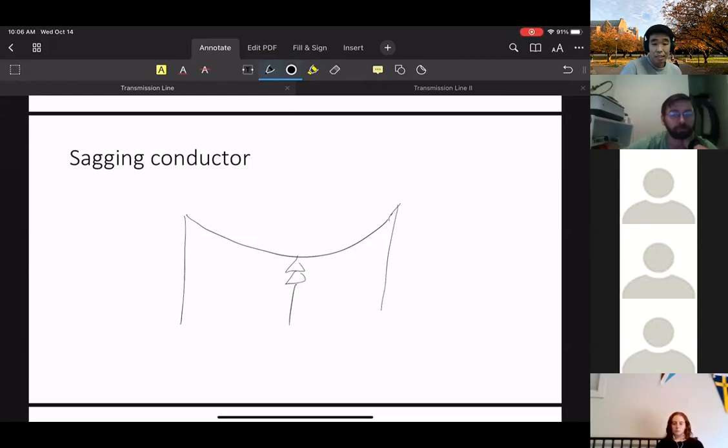That's why we have current limits on transmission lines. The current limit on transmission lines is not when you will melt the transmission line. It's very hard to melt a transmission line; you need a lot of current to do that. What happens, at least for these overhead transmission lines, is that the current limit exists because you don't want the lines to sag too much. That's where current limits come from. This limits current on overhead lines.